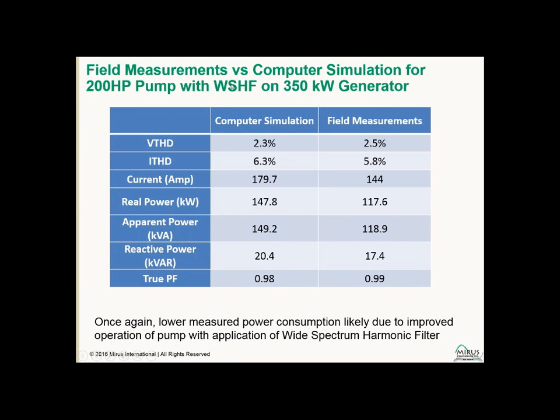When they were running at the 350, you can see the computer simulations and field measurements, again, voltage and current distortion very closely matched the simulations. There was a substantial reduction in power consumption, and improvements, a reduction in kVARs and so on. Again, we believe the improvement in power consumption is due to the fact that the harmonic filter improved the operation of the VFD.